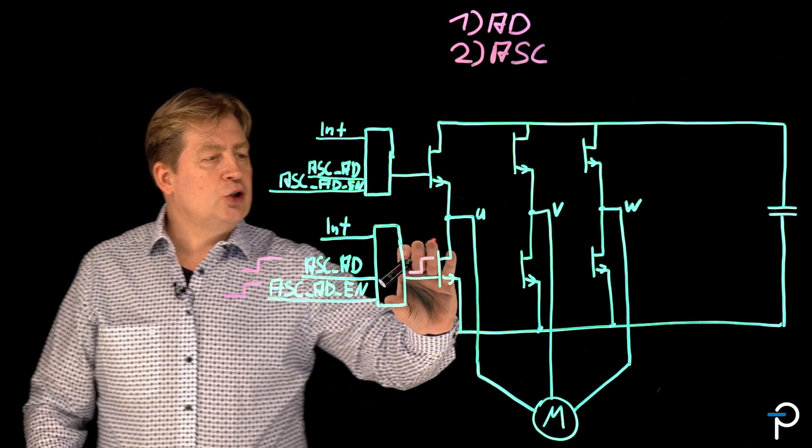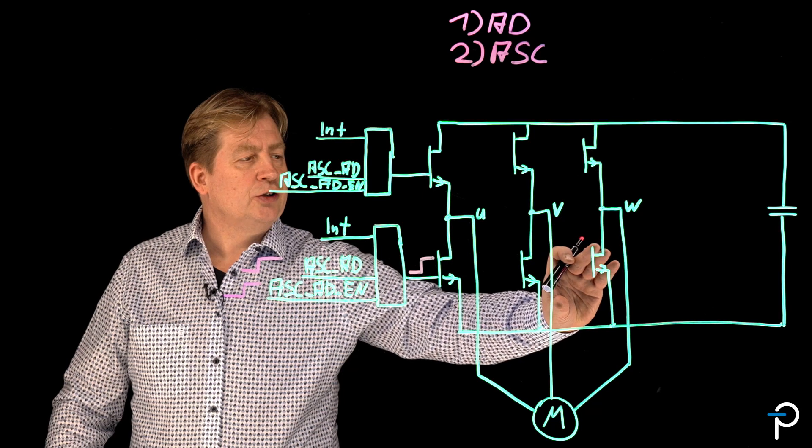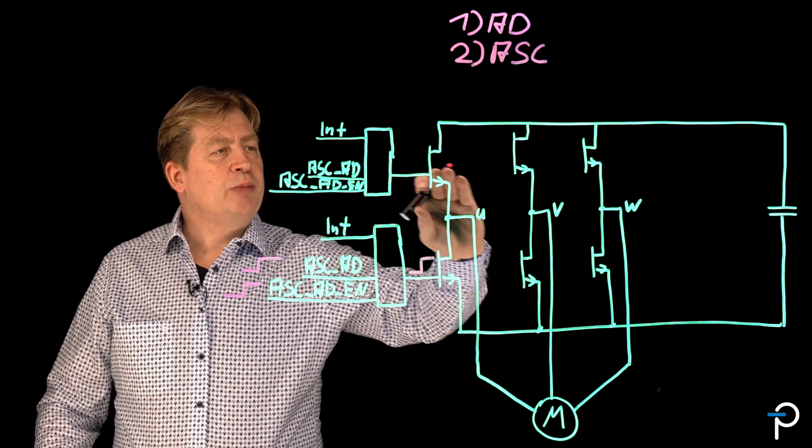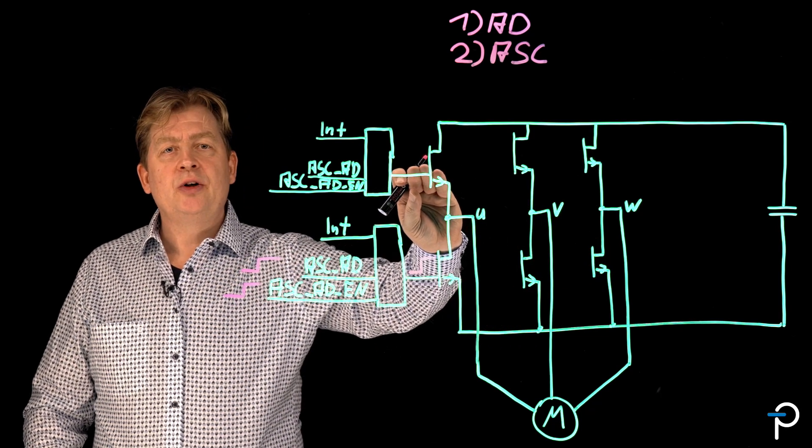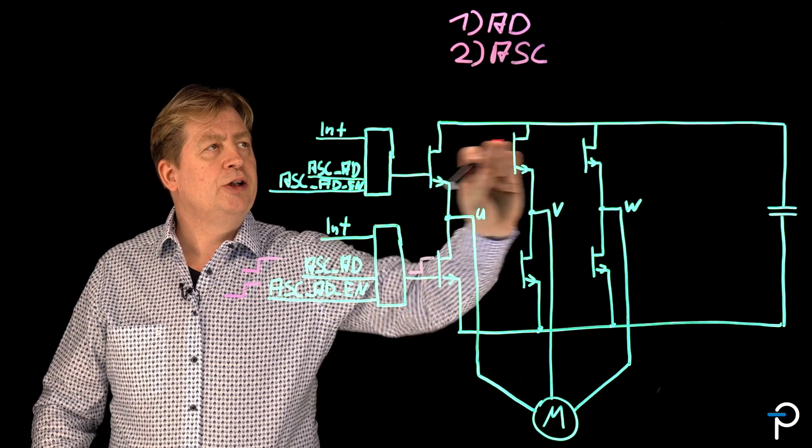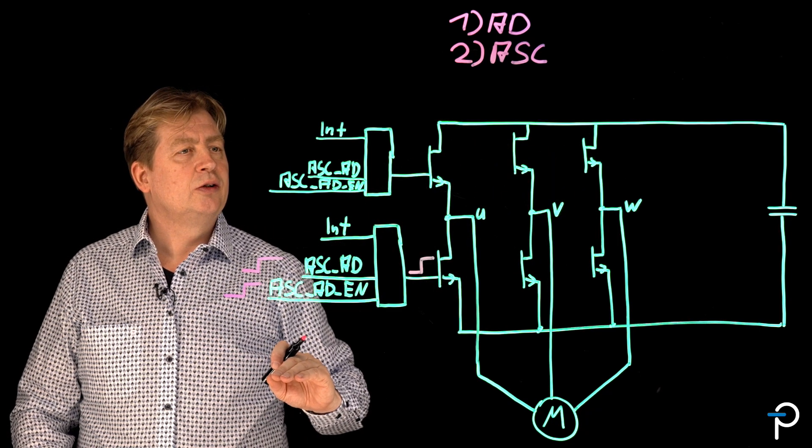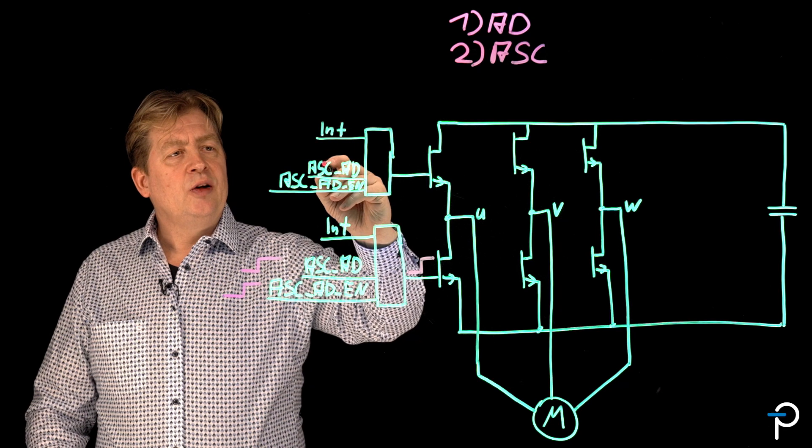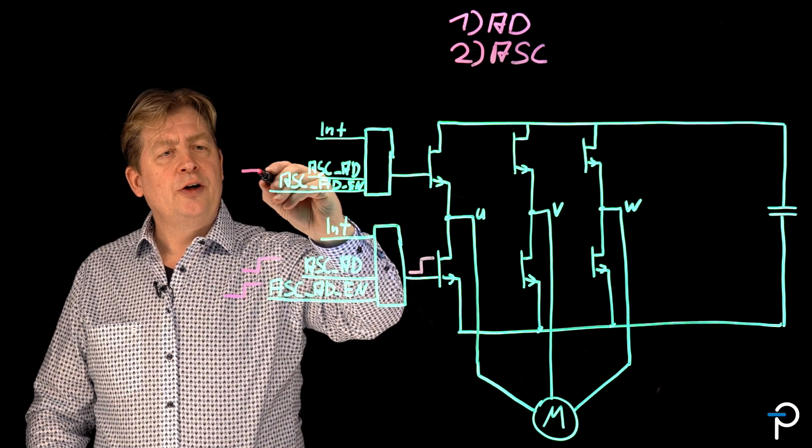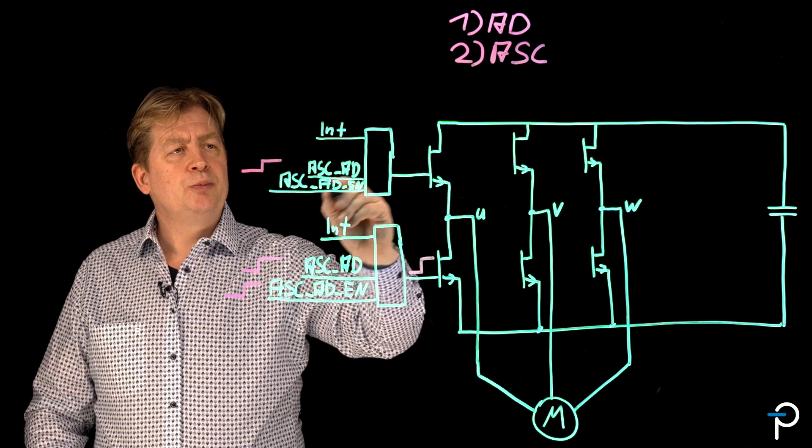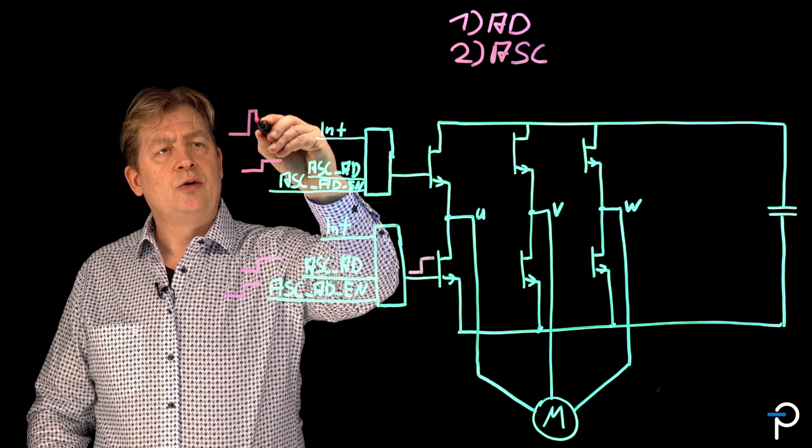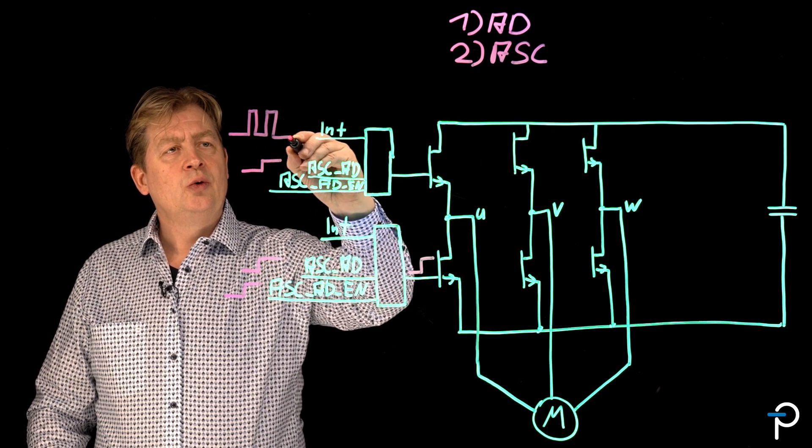In this situation we are shorting the bottom 3 IGBT or silicon carbide and we are pulsing with a lower gate emitter voltage the top IGBTs or silicon carbide. We are applying for this situation 5 volt on a digital input pin and applying again our frequency to the input of the top gate driver.